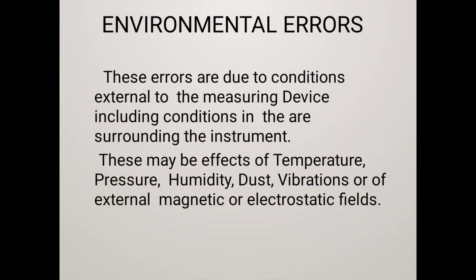Next is Environmental Error. These errors occur due to conditions external to the measuring instrument. The various factors resulting in these environmental errors are temperature changes, pressure changes, thermal EMF, stray capacitance, and cross capacitance. Methods used to reduce these errors include using proper correction factors, using information supplied by the manufacturer, and using arrangements that keep the surrounding conditions constant.